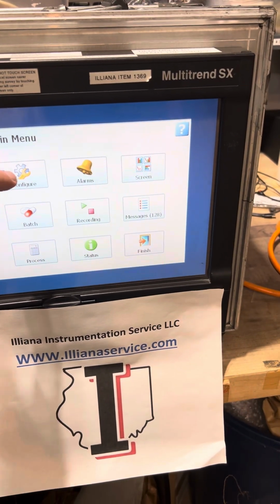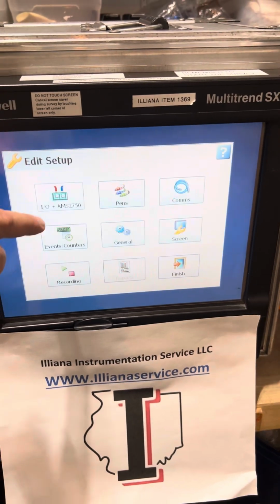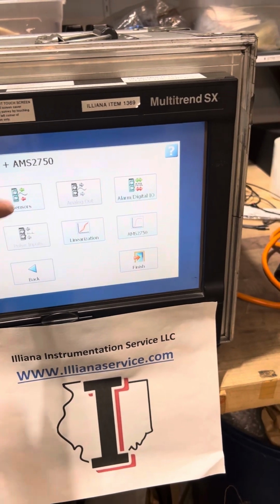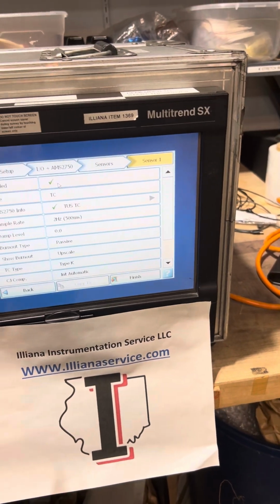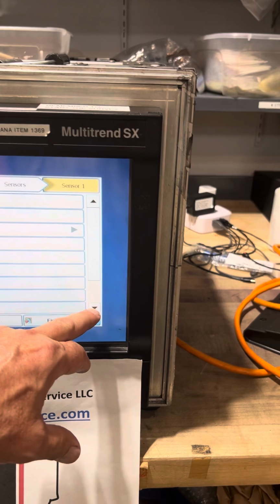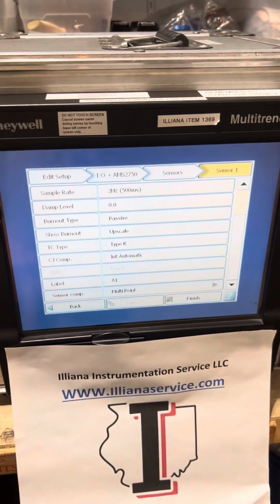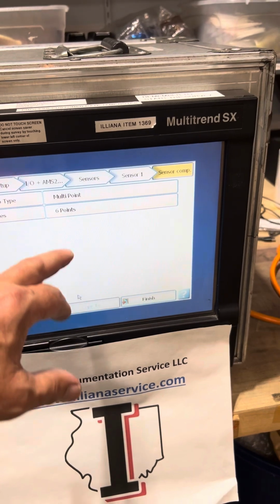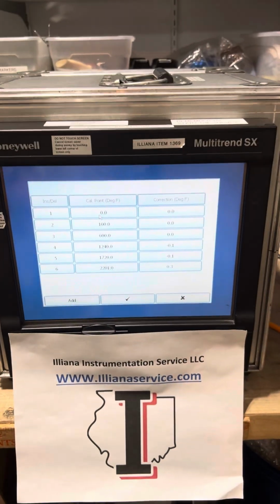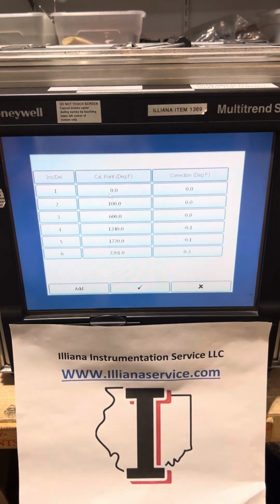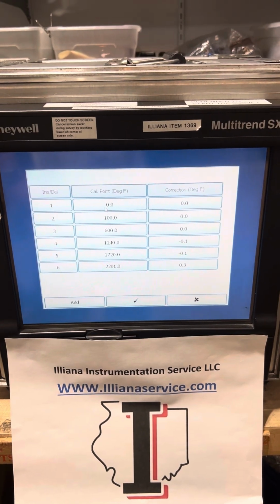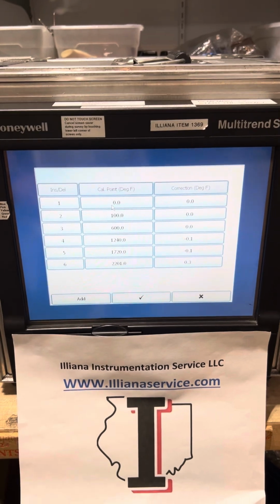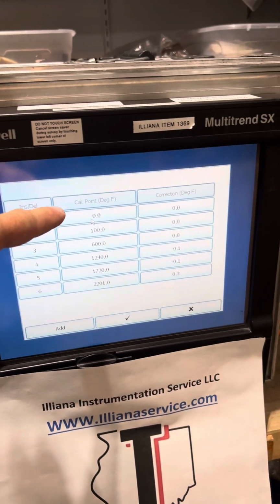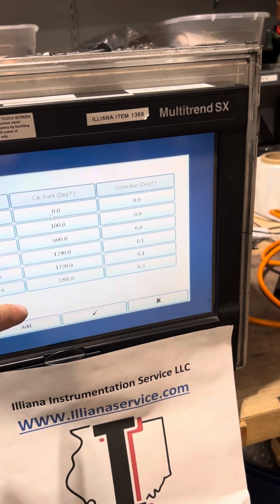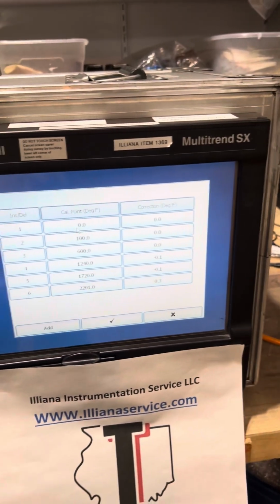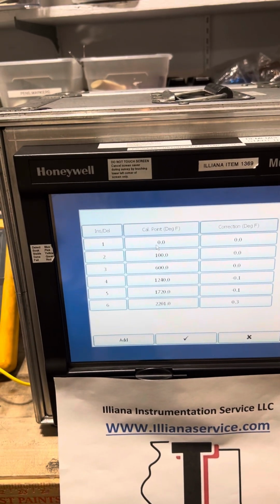So we're going to go to Menu, Configure, Setup, Edit, I/O, Sensors, and we're going to go to Channel 1, which is the one I'm using. And then we are going to scroll down here to a feature called Sensor Comp Multipoint, and if I touch that, it's going to allow me to create a table of corrections or offsets to the recorder at specific temperatures. So this table right now is set up to make corrections at 0, 100, 600, and a couple other temperatures down here. And this value over here is how much of a correction it is going to make.